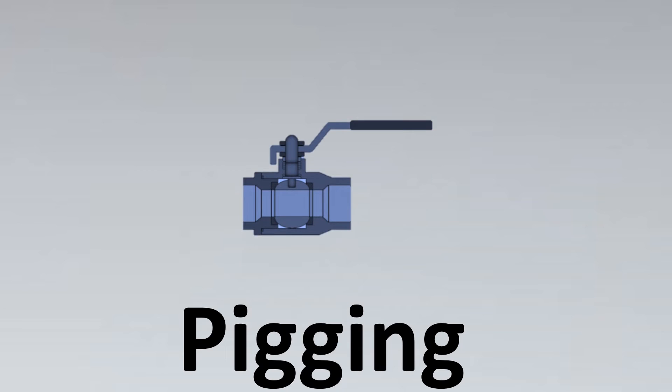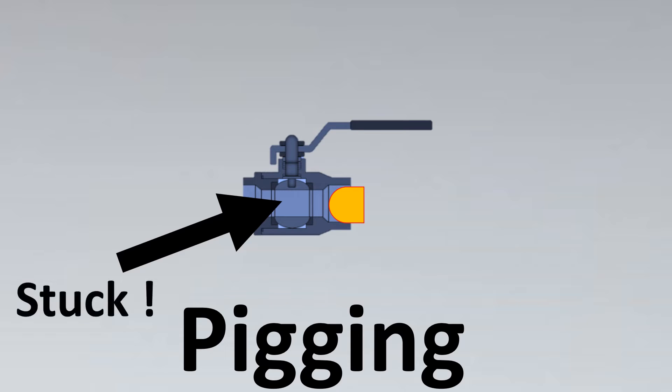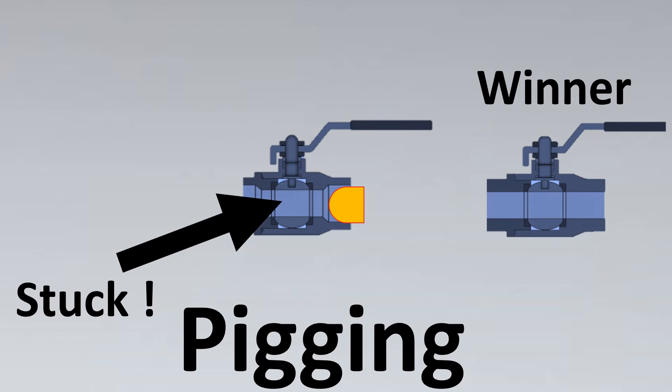Now, how does this have a consideration with our full bore or reduced bore? Imagine this is your reduced bore valve and we insert the pig. What is going to happen? Your pig is going to get stuck inside this valve because the pig size would be that of the line ID, but the reduced bore would have a lesser size, so the pig won't be able to pass through the valve and it would get stuck. Whereas if you take a full bore valve, which is the winner here, the entire pig would be able to pass through the valve. So for such cases we need to consider full bore valves.